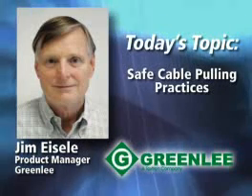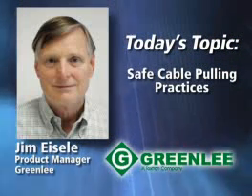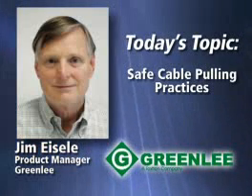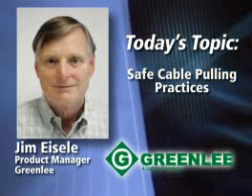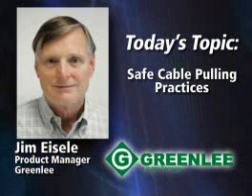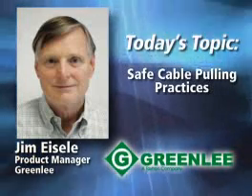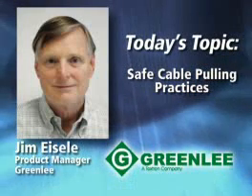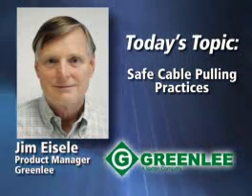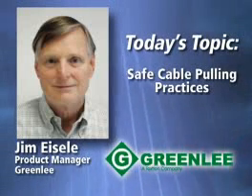But using proper lubrication and connecting the cable to the pulling rope is also important so that you don't create additional force requirements. Isn't the cable's position within the conduit an important factor as well? What about pulling tension? You really can't control, to any great degree, the position of the cables going through a conduit. The code does say that 360 degrees is the maximum amount of bend that a cable pull should be done through, and they require a junction box in the middle of a run if the number of bends exceeds that 360 degrees. Besides the obvious safety concerns, can you talk about the expense of not doing it right?